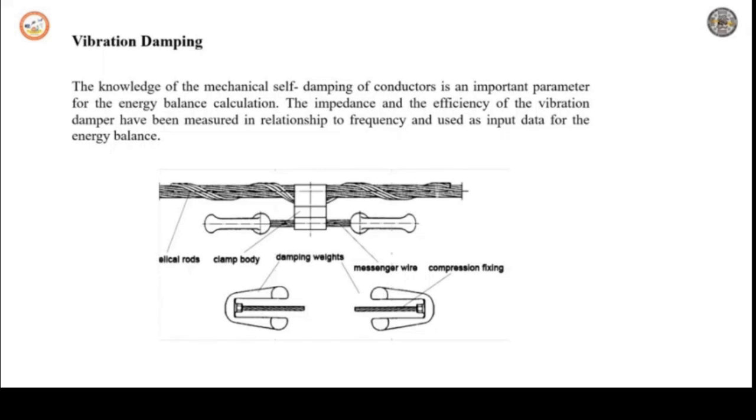The main feature of this damper is the grip of the damper. The conductor uses only one bolt. Another feature is that these dampers can be fastened to the conductors even though the line is alive, using special long-handled tools. You can see the complete arrangement of the Stockbridge type damper.